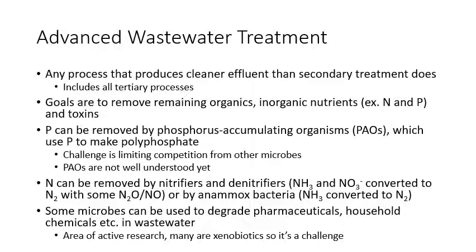Then for nitrogen, you can remove that in a couple of different ways using microbes. You could use nitrifying bacteria and denitrifying bacteria sequentially. The nitrifiers would first be converting ammonia to nitrate, and then the denitrifiers would be converting nitrate to molecular nitrogen and also some nitrous and nitric oxide. Usually if you have nitrogen polluting wastewater, it would be either in the form of ammonia or nitrate, some type of fixed nitrogen. Those can both be removed if you're using nitrifiers and denitrifiers. The issue is that, of course, you're producing greenhouse gases.